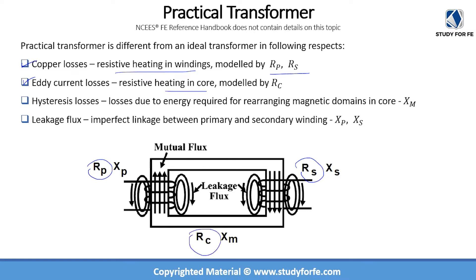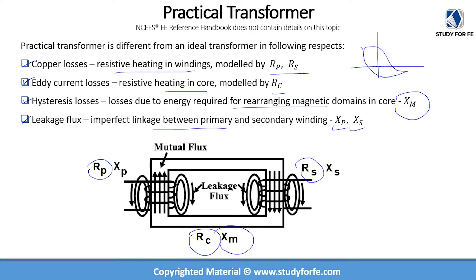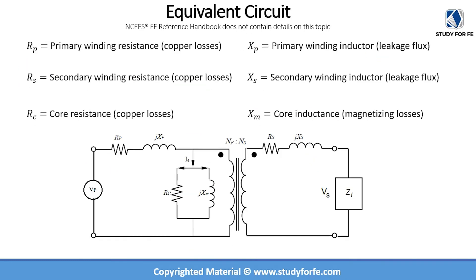We also have hysteresis loss, which is the energy required for rearranging magnetic domains — the magnetic dipoles must be rearranged every time the AC current changes direction, and this is modeled by X_m, the inductive magnetizing reactance. Finally, leakage flux represents imperfect magnetic linking between primary and secondary windings, and is modeled as X_p and X_s on the primary and secondary respectively.